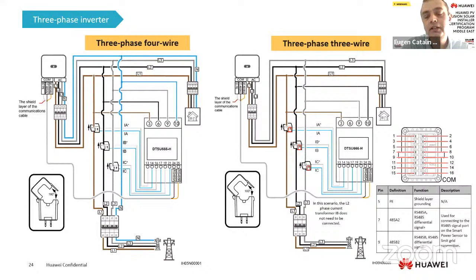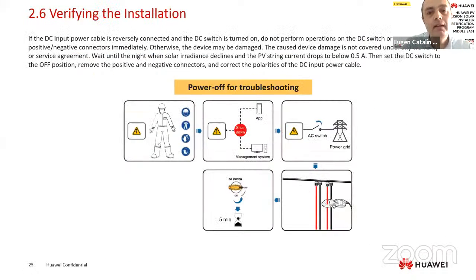Again, install the CT and the meter on the main breaker, on the main cable. Check the meter measurement before powering on the inverter. All the active power should be positive. After we perform a correct installation, of course, we need to measure, check the polarity, and check that the voltage is in range with the inverter. If we have a single-phase inverter, 600 volts on DC. If we have a three-phase inverter, maximum 1100 volts. Anyway, you design the strings before, you measure the AC, and you power on the inverter.